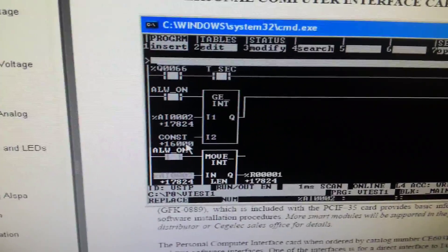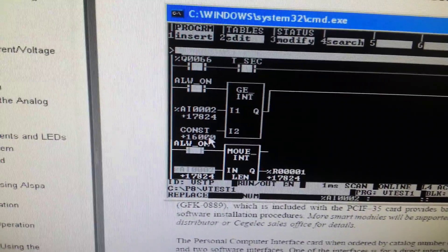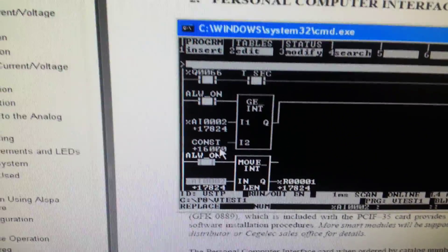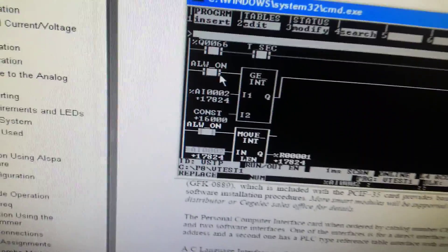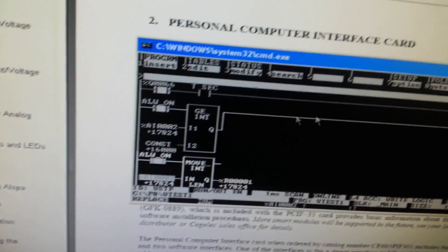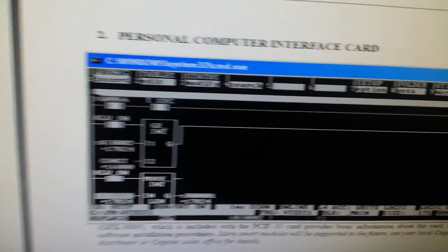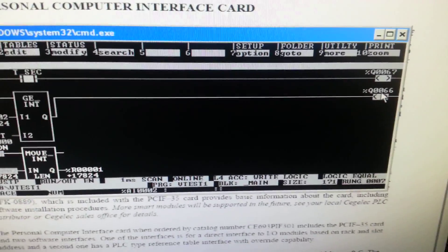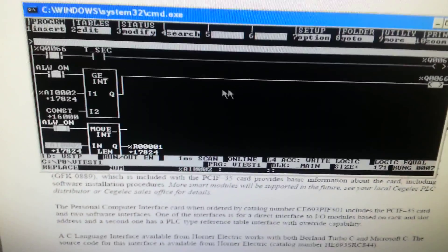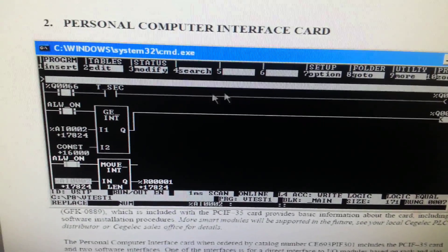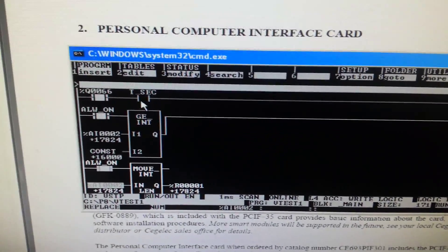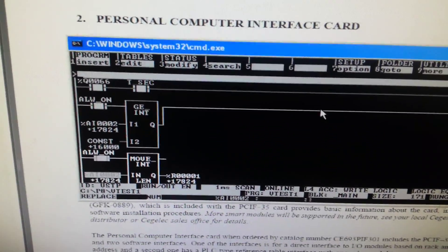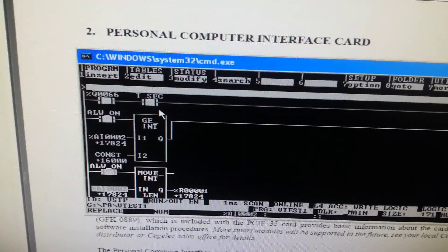The scale is 0 to 32,000, so 16,000 corresponds to 12 milliamps. I set the limit to 16,000. When the current reaches 12 milliamps — that is, when AI 002 reaches 16,000 — the block output will energize, energizing Q 0066.